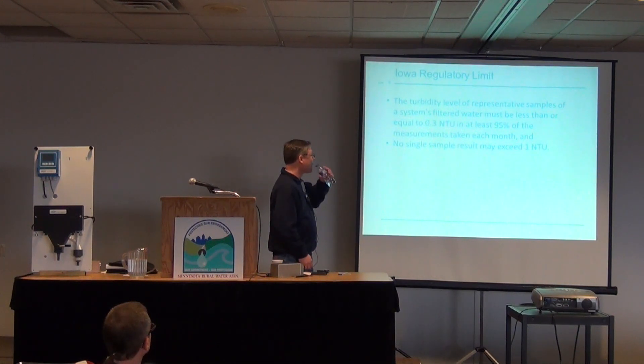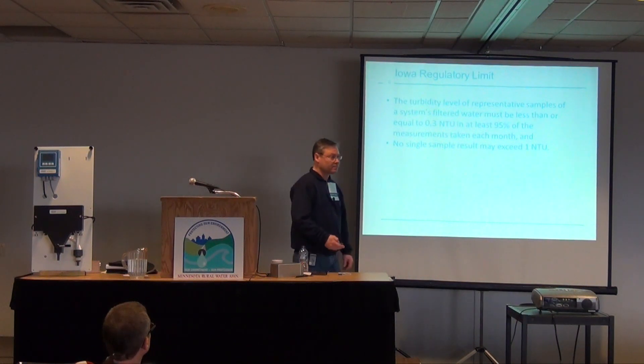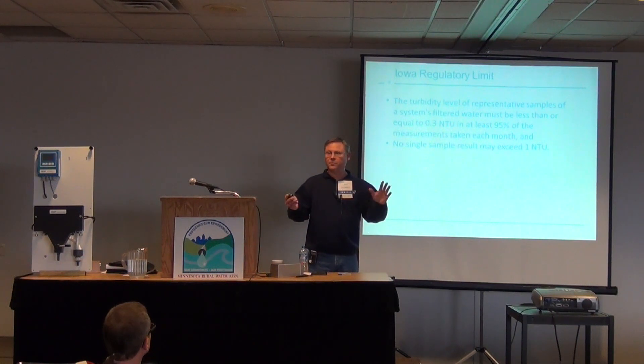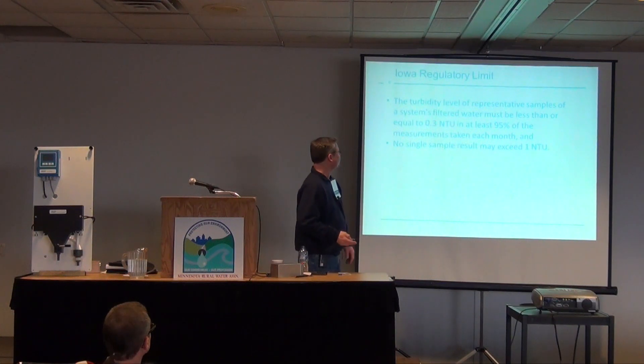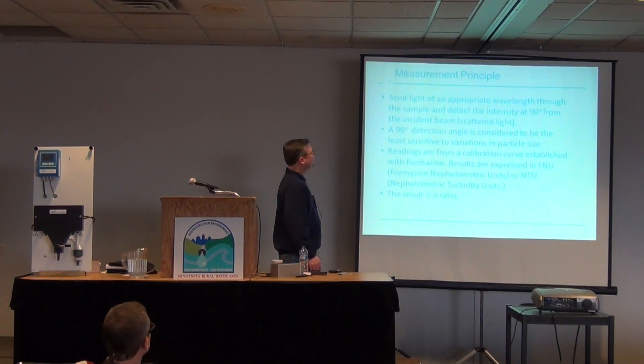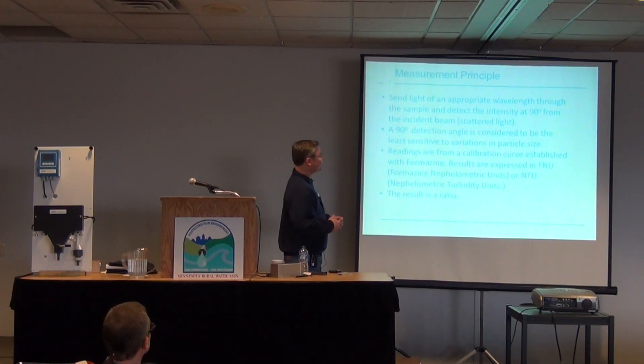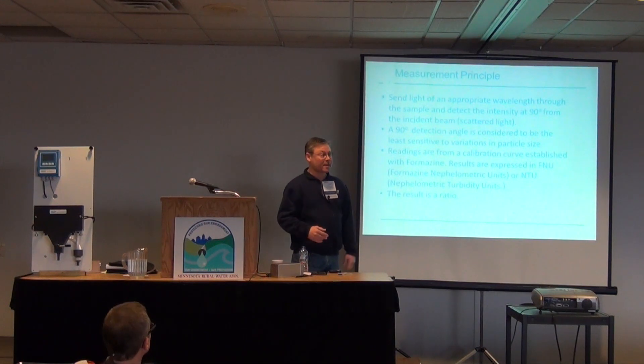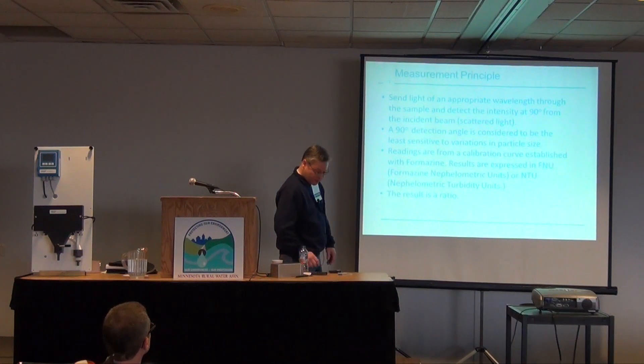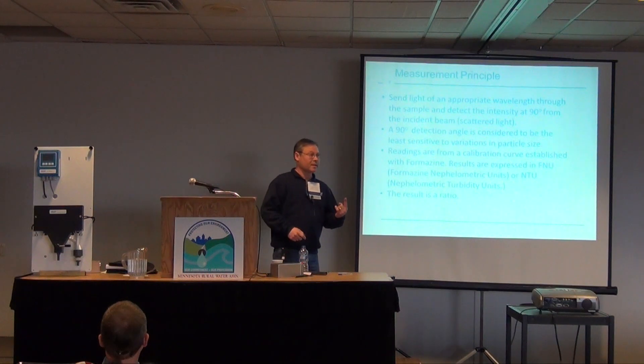This is a standard for drinking water. The EPA-approved method — Method 180.1 — calls for a white tungsten light source at 515 nanometers. That's the appropriate wavelength. We actually make an instrument that uses a red LED light source at 860 nanometers, which can measure higher ranges.